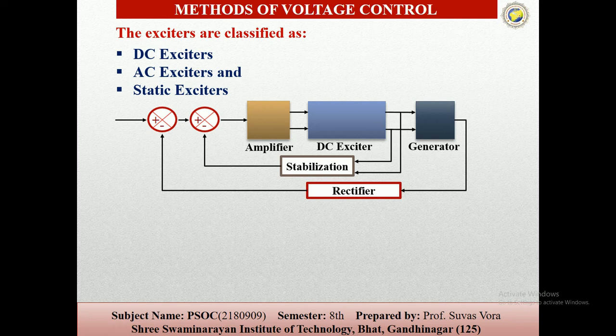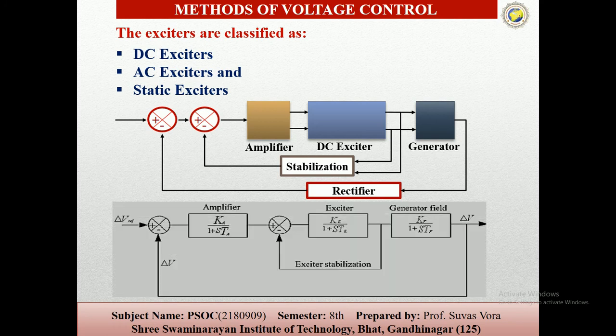So the generator terminal voltage is compared with the set reference voltage to get the voltage error signal. This signal is given to the voltage regulator. The regulator output is given to the block with transfer function KE upon 1 plus TS. The exciter output is given to the field winding, which adjusts the generator terminal voltage. So now you can see the basic block diagram of this system: the amplifier, exciter, exciter stabilization, then generator field.